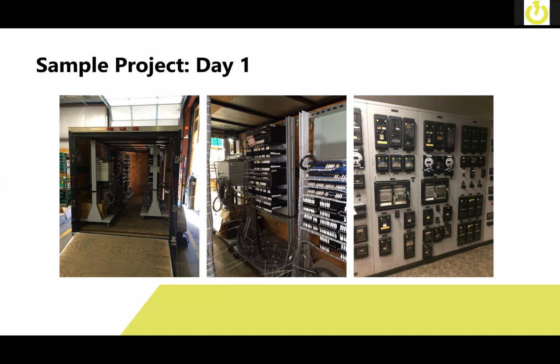We ship them in panels that are prefabricated with the relays fully hung, terminated as much as possible. Everything on those panels is pre-terminated, pre-landed. It's got wire labels on it showing to and from wire destinations. And it's also mounted in secure racks for transportation. That way it doesn't get jostled or damaged during transport to the facility. And you can kind of see through some of these pictures where we mount them on our panels, where we hang them whenever we go to put them in the trailer. And then on the far right-hand side is a before picture of the customer's facility.